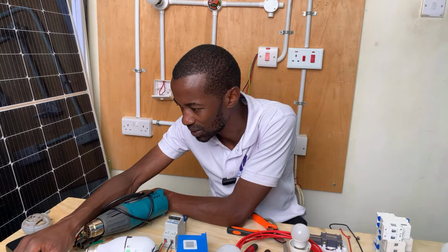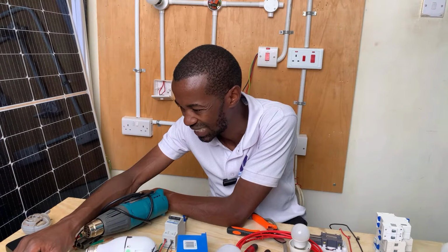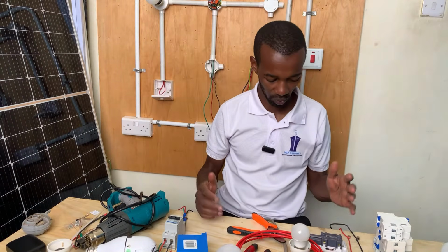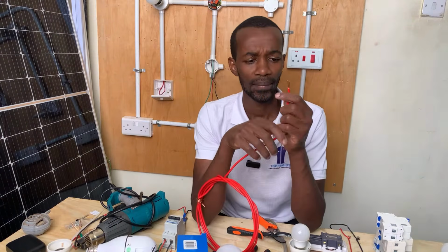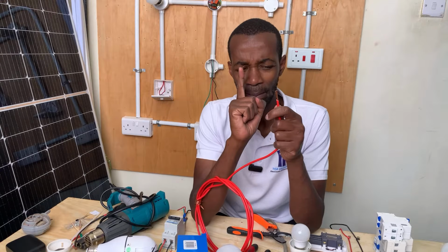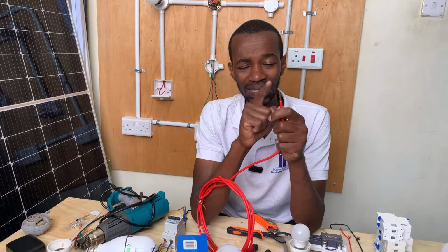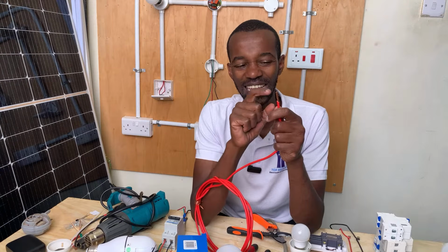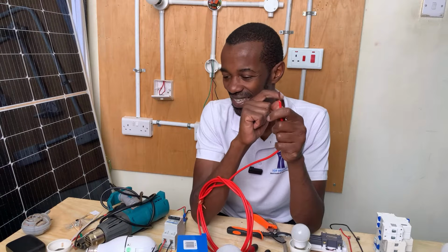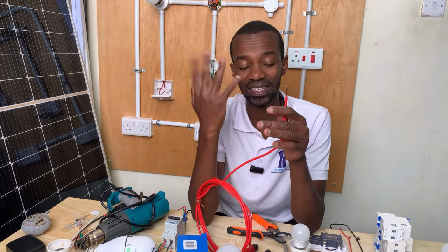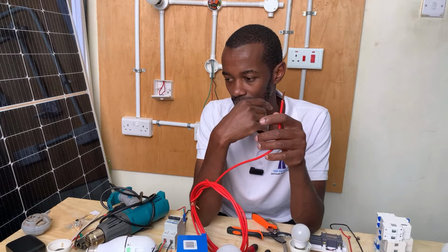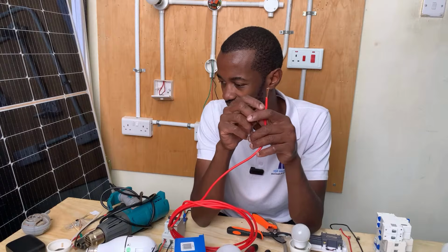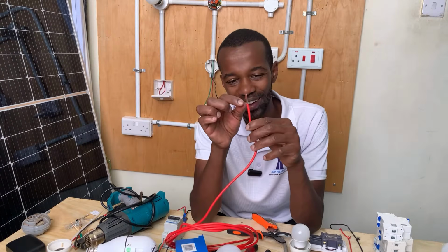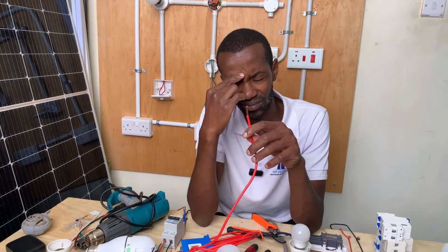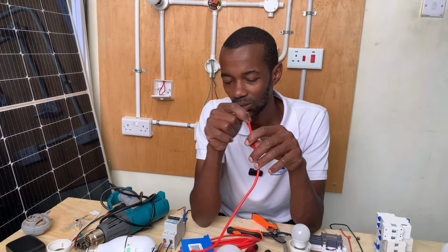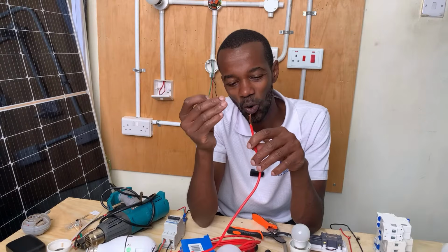Yes, compromising on the number of strands is detrimental - it increases the resistance. Remember we learned in high school physics that the resistance of a wire is determined by the size of the wire, the material of the wire, and the length of that wire. The longer the cable, the higher the resistance to the flow of current. The thicker the wire, or the bigger the cross-sectional area - can we say cross-sectional area or diameter - the lower the resistance to the flow of current.